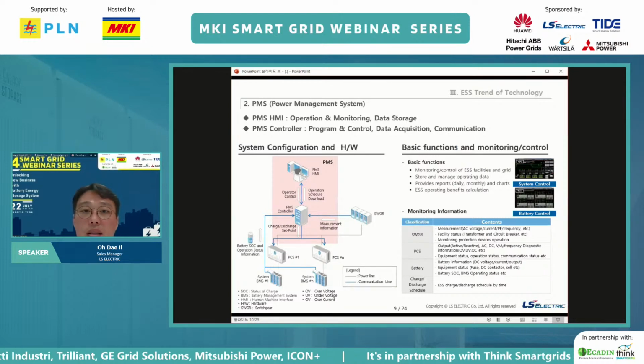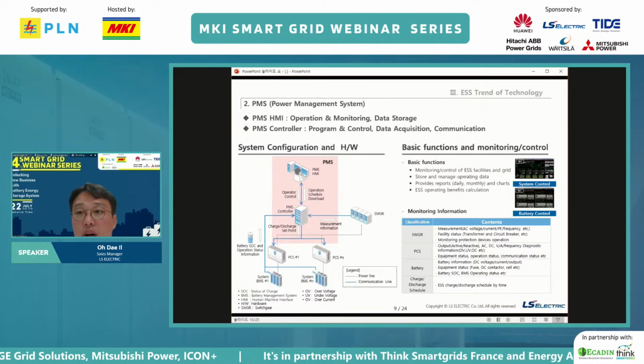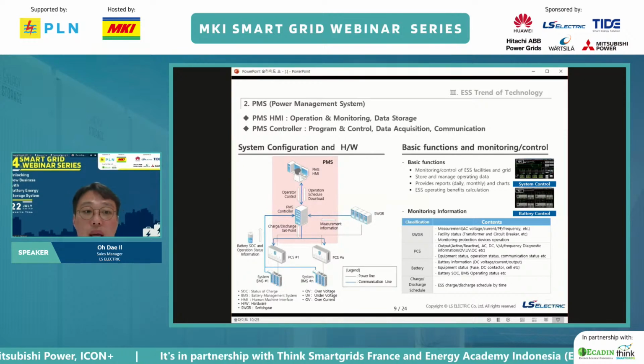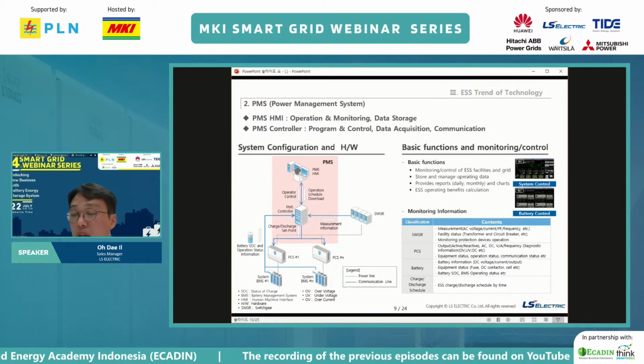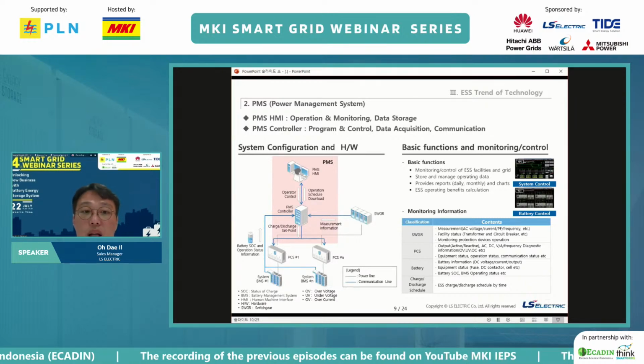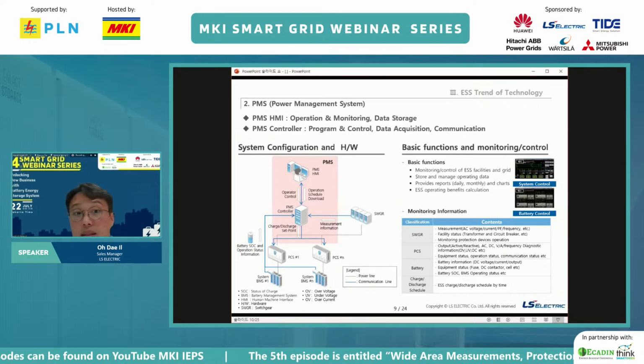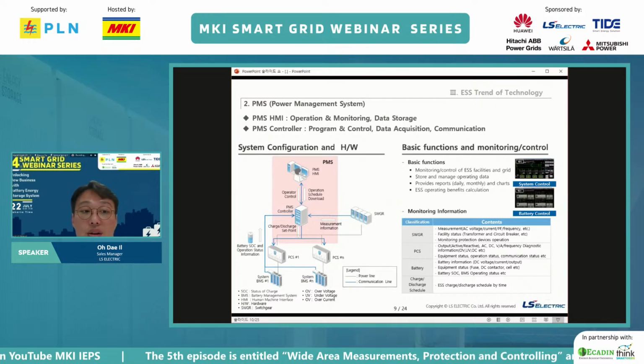PMS is an essential technology of the ESS system. PMS, which serves as the control tower of the ESS, is software that adjusts the amount and time of charge and discharge of the ESS through control of the battery. It is a system that analyzes charging and discharging data of the ESS in conjunction with sensors and measuring equipment, and controls the ESS to operate at optimal efficiency.